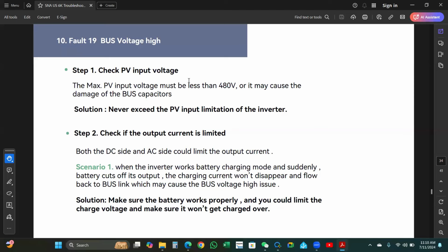Step 2, check if the output current is limited. Both the DC and AC side could limit the output current. Scenario 1: when the inverter works in battery charging mode and the battery suddenly cuts off its output, the charging current won't disappear and will flow back to the bus link, which may cause the bus voltage high issue. Solution: make sure the battery works properly, and you could limit the charge voltage and make sure it won't get overcharged.